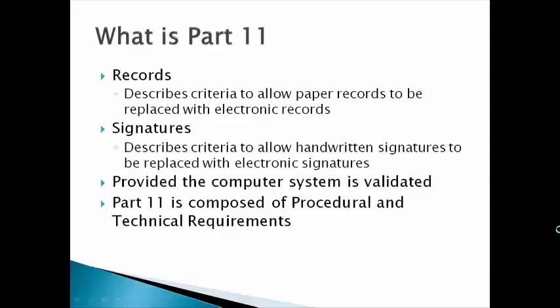Part 11 deals with records. It describes the criteria to allow paper records to be replaced with electronic records. It discusses signatures and describes the criteria to allow handwritten signatures to be replaced with electronic signatures. And all this is predicated on the computer system housing the records and signatures being validated according to standard computer system validation procedures.